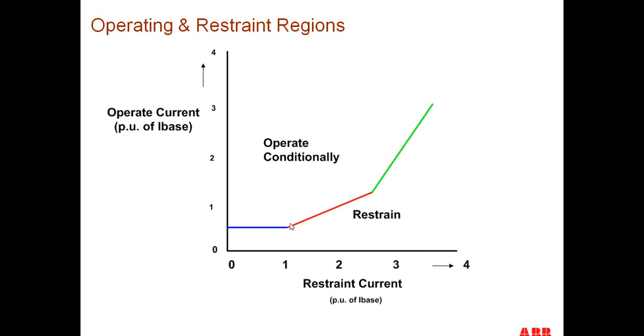Then when we get between 1 per unit and 3 per unit of current, we feel that you're going to get some error current out of the current transformer. So we increase the operate current for this given amount of restraint current, so that it compensates for this error current from the current transformer. Then when we get about 3 per unit or so upwards, at a much higher current level, we're pretty sure we're going to get some kind of CT saturation. Now we have to have much more operate current for a given amount of restraint current before the relay operates. Hence the 3 different parts of the curve that you see.